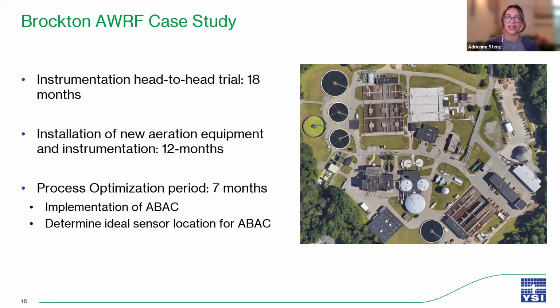And then this is a case study done at Brockton Advanced Water Reclamation Facility in Massachusetts. They did a case study with our ammonia sensors during a major upgrade that involved installing all new aeration equipment and instrumentation in an effort to improve their nitrogen removal and improve their aeration efficiency. The first step of this big study was a head-to-head trial with 3 manufacturers' ion selective electrode ammonium sensors to determine which would work best for them, since having a reliable ammonium sensor is important for ammonia-based aeration control. The trial between the 3 manufacturers' ammonia sensors was done over 18 months, and they eventually chose YSI based on our sensor's accuracy, the lifetime of our sensor's electrodes, and its ease of maintenance.